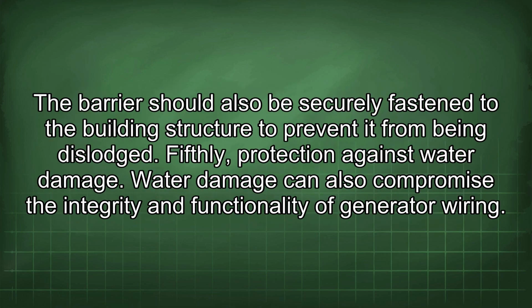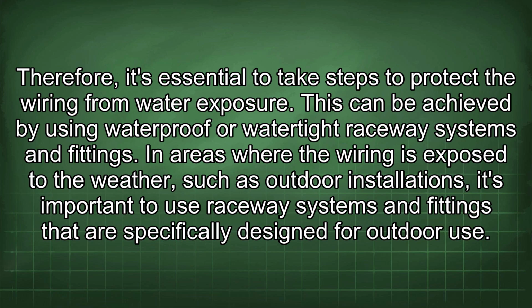The barrier should also be securely fastened to the building structure to prevent it from being dislodged. Fifthly, protection against water damage. Water damage can also compromise the integrity and functionality of generator wiring. Therefore, it's essential to take steps to protect the wiring from water exposure. This can be achieved by using waterproof or watertight raceway systems and fittings.